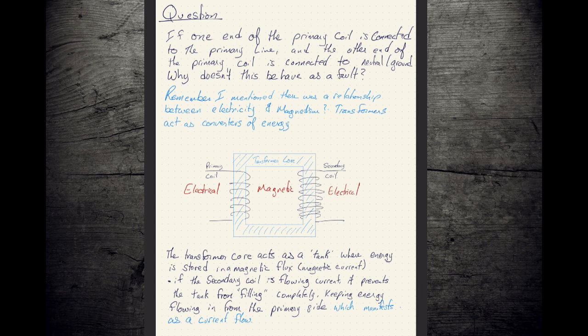And so on the secondary side, we get this flow of magnetic energy going around the transformer core, being pulled, and that flow is being triggered by the energy in the primary side. And it's going to flow through here, and it's going to induce a voltage on our secondary terminals. And so the transformer core sort of acts as a tank.